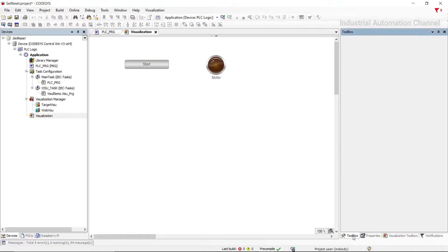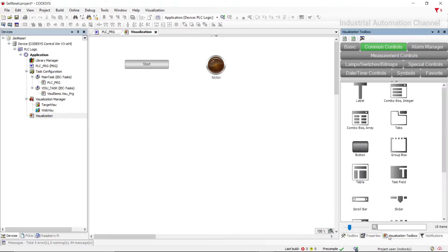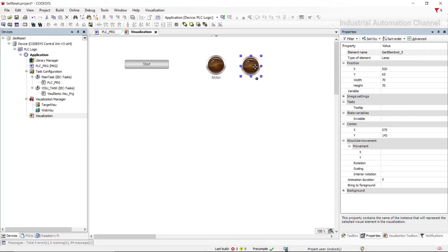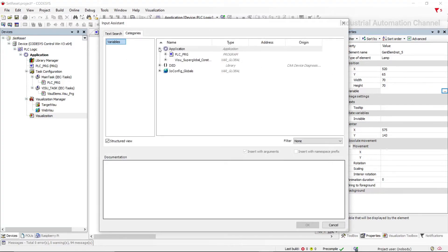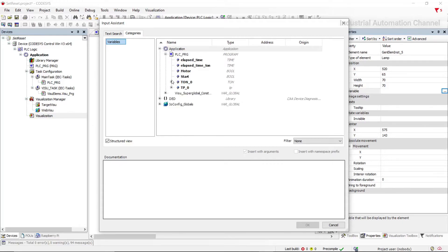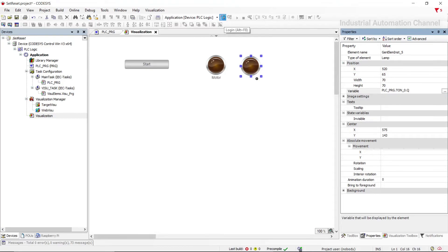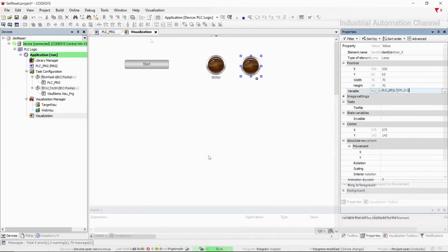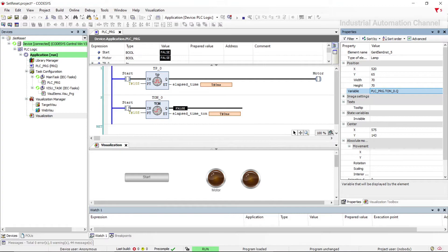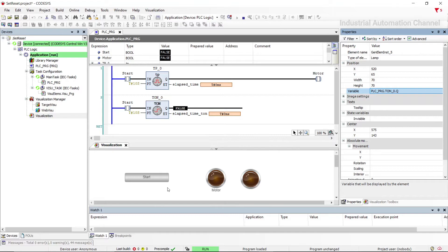Let's insert another pilot lamp for the output of this timer. As a variable we can use the sub-variables that belong to the timer — Q is for output. Now if I run the program, input is false and output is also false. As soon as I press start, the elapsed time starts to count, and 10 seconds after that the output of the timer will be activated. Whenever I change the state of the input to false, the output of the timer will be turned off.